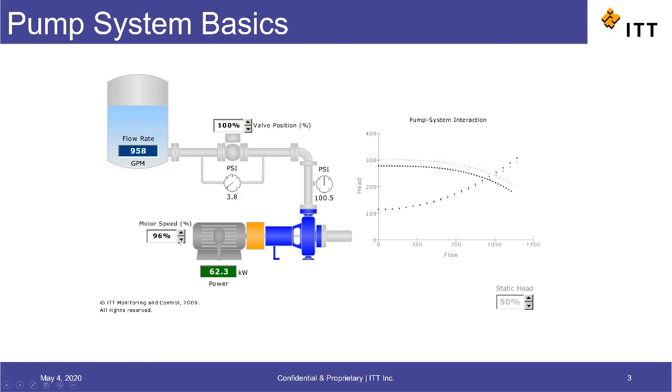What happens is we leave the system curve in its original shape with the discharge valve fully open. And as the motor speed and therefore the pump speed come down, we're shifting the pump curve down until it intersects with the system curve close to our desired flow rate.